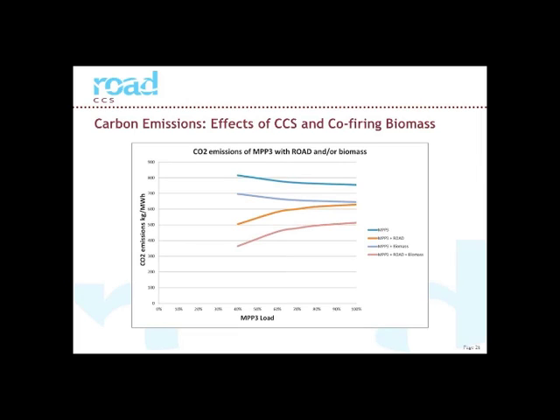in part load of MPP3, where we will even have lower specific emissions than in full load, because the carbon capture plant can run at full load when MPP3 is in part load. In the bottom lines you see the combined effect on the CO2 emissions of both the CCS plant running and biomass being fired at around 20% of the weight percentage of the total fuel flow to the capture plant.